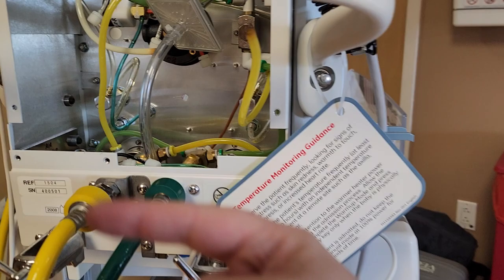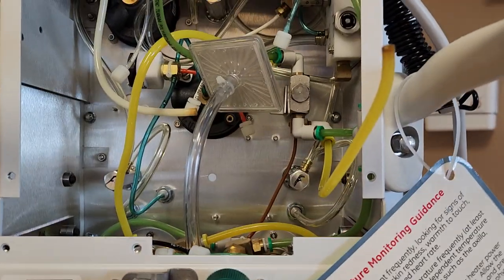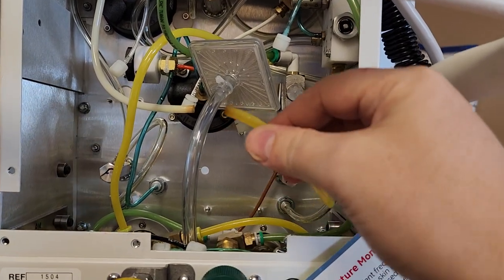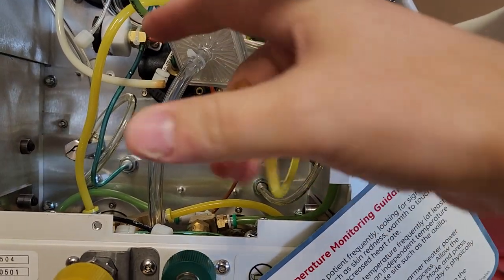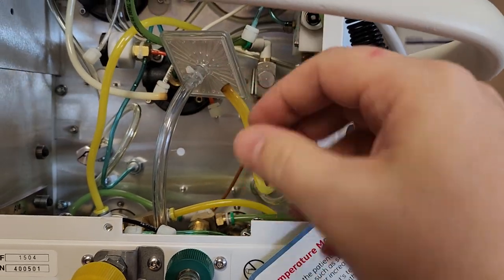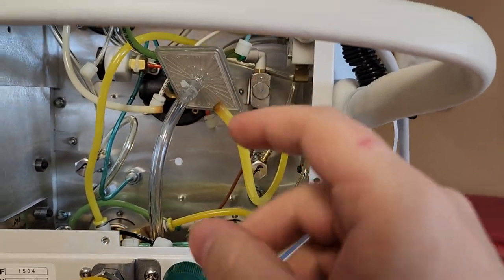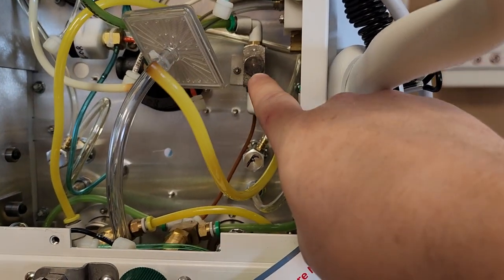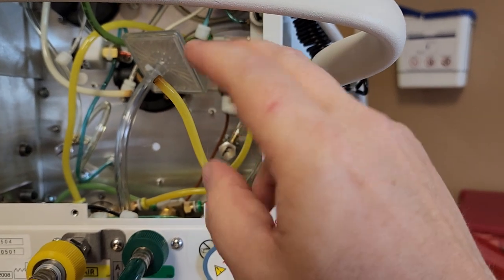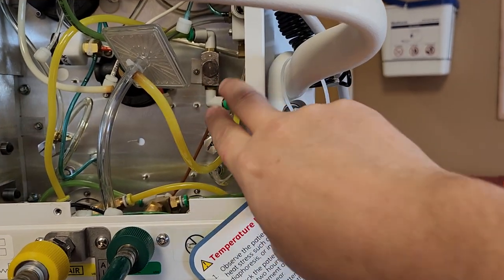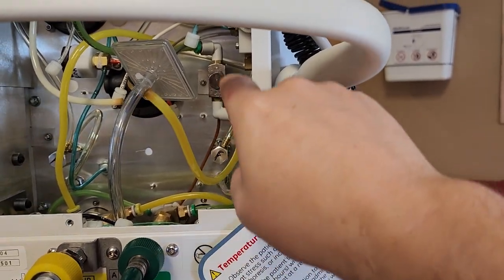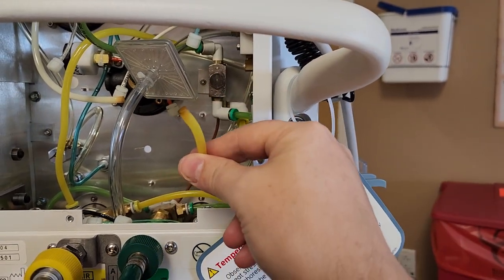The blender itself is currently getting rebuilt in this room as we speak, but in its absence here's something that you should notice. First off, yes these need to be trimmed back because they're discolored and they're pre-crimped. That can be a problem for leakage in the future. But these guys right here which come up to your pneumatic switch—it's a dual gas feed switch—so you have oxygen and you have med air that are switched when you turn it on. Here's the thing: I have pressure as soon as I connect this to the wall when it's in the off position.